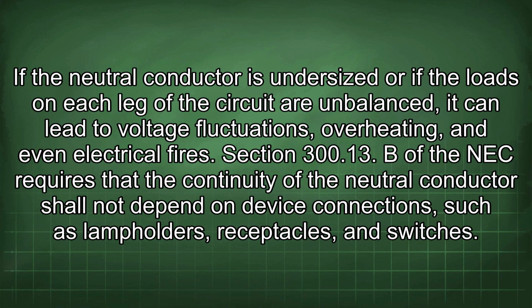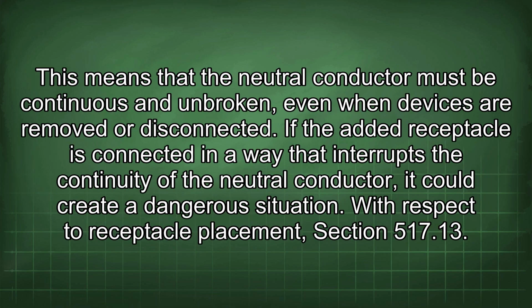Section 300.13(B) of the NEC requires that the continuity of the neutral conductor shall not depend on device connections such as lamp holders, receptacles, and switches. This means that the neutral conductor must be continuous and unbroken, even when devices are removed or disconnected. If the added receptacle is connected in a way that interrupts the continuity of the neutral conductor, it could create a dangerous situation.